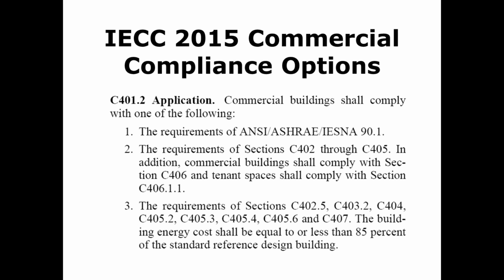There are 3 ways to comply with this code. We're only going to talk about one of those today. But the first way to comply is to follow ASHRAE 90.1. ASHRAE 90.1 is the energy standard for the entire country. It's the basis of this code anyway. But if you don't want to use this code book, you could just follow ASHRAE 90.1 and you would automatically comply. ASHRAE 90.1 has several compliance paths of its own that we're not going to talk about today, but you could certainly do that.